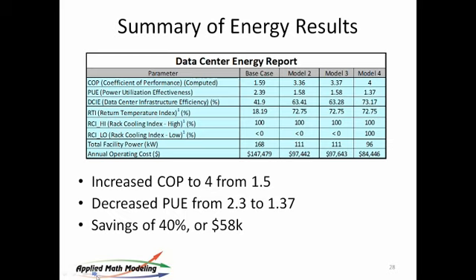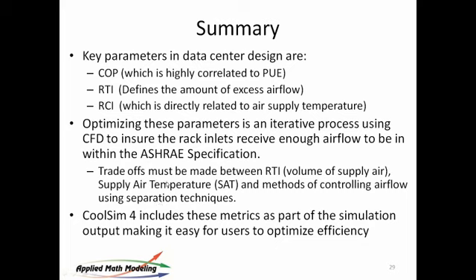So that's a quick overview in the time we have. We're just about up on 4 o'clock. So let me just summarize. We defined a few key parameters. We defined COP of the room, which is very highly correlated to PUE. We defined RTI and RCI as two other metrics that we use to measure efficiencies in the room. We then optimized these parameters in a process that used CFD to make sure that whatever decision we were making would work and still keep our racks within specifications. And you do need to make some trade-offs between RTI, supply air flow, and supply air temp to make sure that they are balanced. And you can do this all in CoolSim, making it really quite easy to optimize.